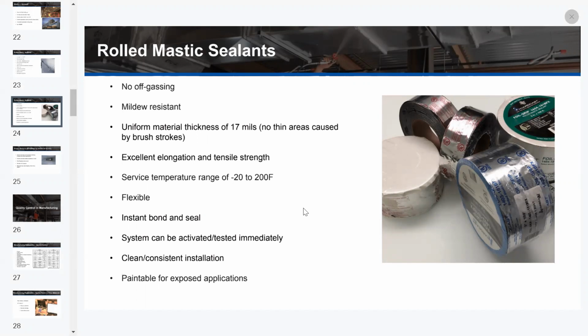So rolled mastic sealants have many other characteristics as well. Since they're 100% solids, there is no off-gassing. They're mildew resistant. They're uniform thickness, so you have a good, homogeneous and consistent install. They offer good elongation, excellent tensile strength, and a really wide service temperature range, -20 to 200 Fahrenheit. Flexible, it's an instant bond and seal, which allows the system to be tested and/or turned back on immediately. And the facer with consistent mil thickness gives a clean and consistent installation that can also be painted for exposed applications.